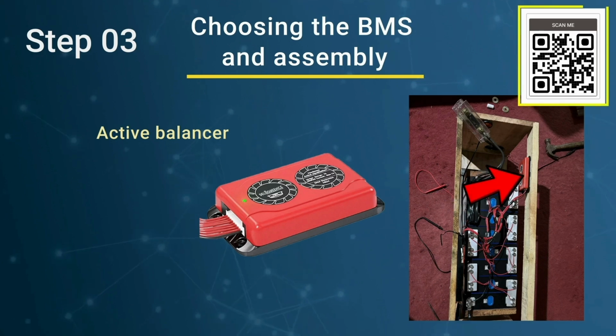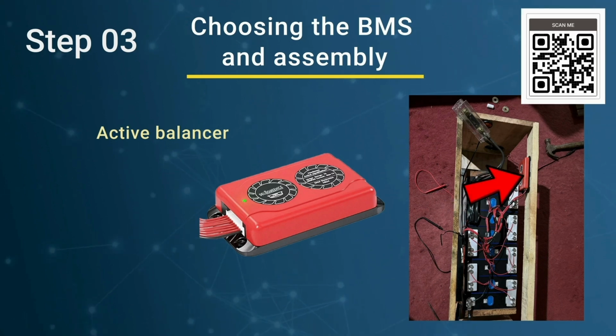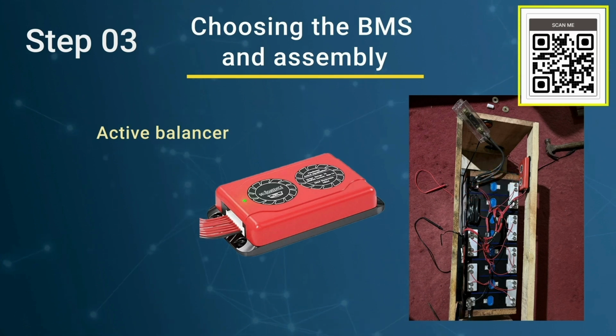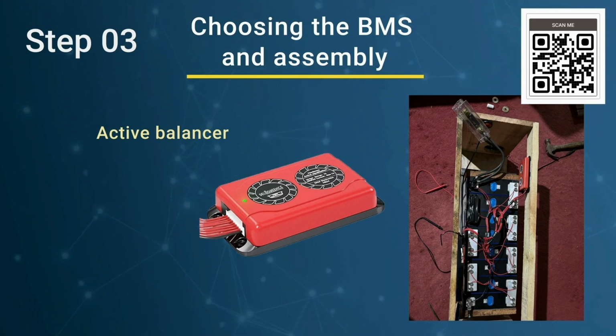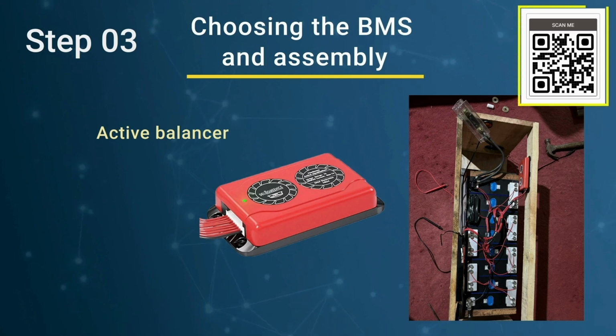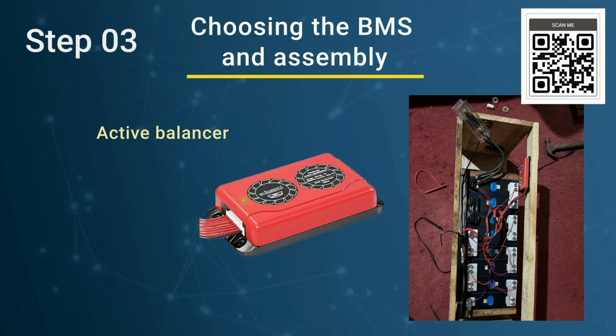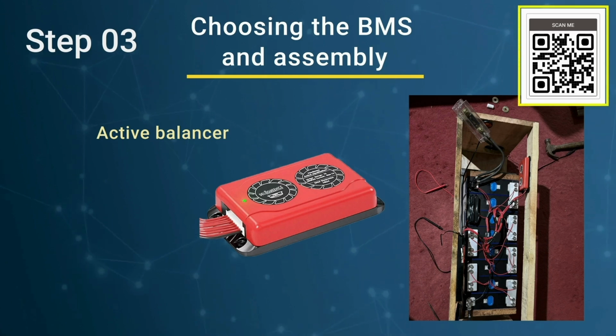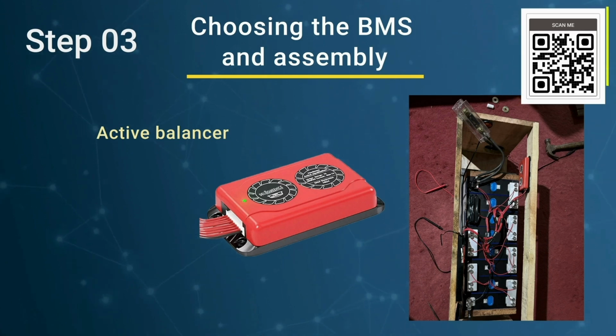Passive or active cell balancing ensures that all cells maintain similar voltage levels, which extends battery life and improves performance. If the BMS does not include active balancing, as in the case with your DALY BMS, you will need to purchase a separate active balancer to keep the cells balanced during charge and discharge cycles. Active balancers are more efficient as they redistribute energy between cells rather than wasting it as heat.